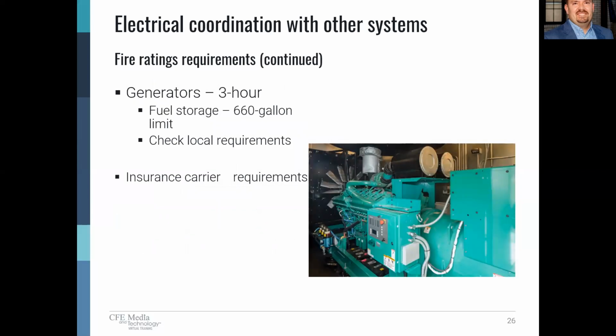So again, in the case of a healthcare occupancy, as an example, where you often find generators that are interior to a building, the generator room is required to be 3-hour rated. And there's a limitation on the amount of fuel that you can store indoors. And that limit is 660 gallons. But in some jurisdictions, as an example, Chicago, they have a stricter requirement on the limitation of fuel storage in the building. So check your local requirements on that. The other thing to consider too is insurance carrier requirements. Your owner is going to have an insurance carrier, and they are going to have specific requirements as well on a project that we need to be cognizant of.